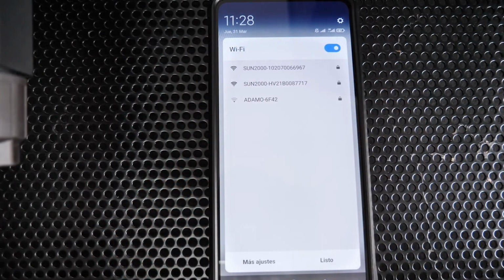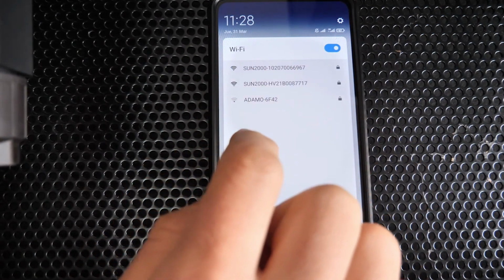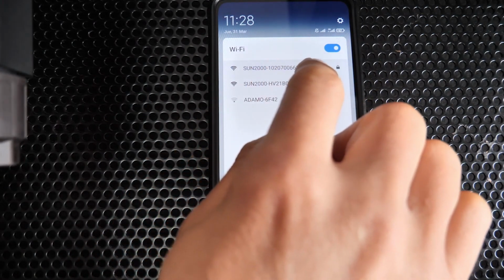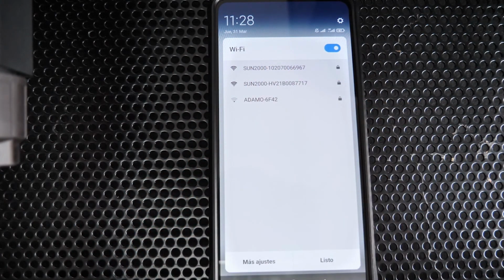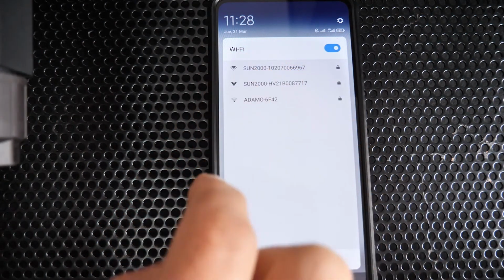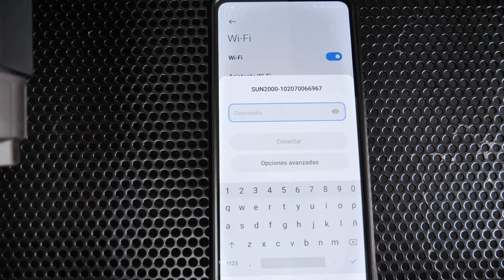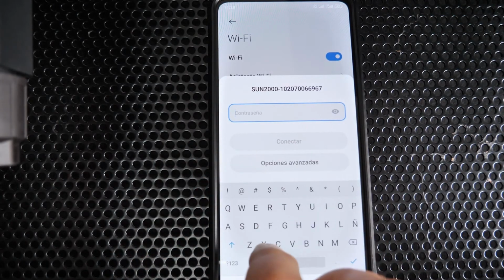by connecting directly to the network generated by the inverter itself. You can see that we have 2 networks. The numbers of each network correspond to the serial number of the inverter. In this case, the master inverter is the first one. Then we would connect directly to that network. We have to enter the password that comes by default, which is 'change me'.